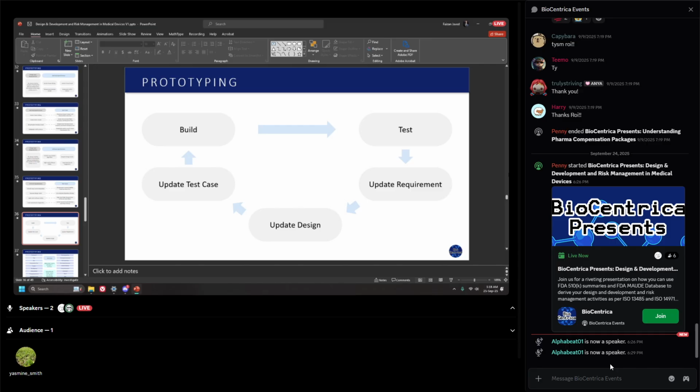So if you test your valving mechanism that many times and it's still working properly, you basically run it that many times and then do the essential performance for that particular subsystem, and see if it falls under your set criteria. If it does, then congratulations, you have a reliable subsystem, and you can make it better if you have to. And similarly, you do that for all of your subsystems and make sure that they are all reliable before you put all of them together.